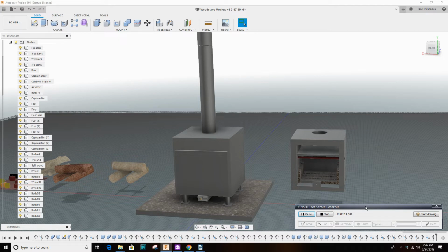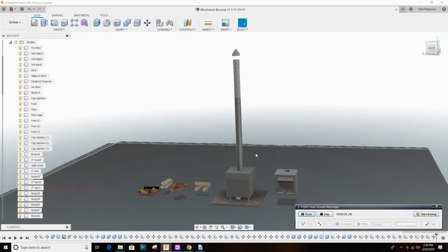On the left here we have a wood stove. We call it a wood stove because you can walk around it. If it's an insert, it's in masonry and you can't really see the back of it. This wood stove is on a non-combustible surface here. It's got 4 legs and 3 sections of stack with 1 exterior stack and a cap. The cap is to let the exhaust gases out, but also let rainwater not go into the stove and down the tube.